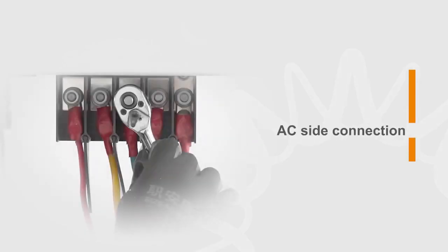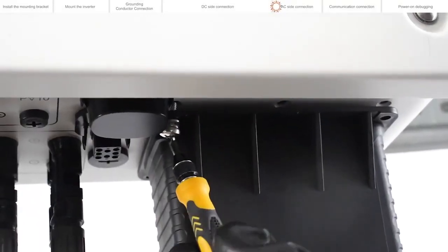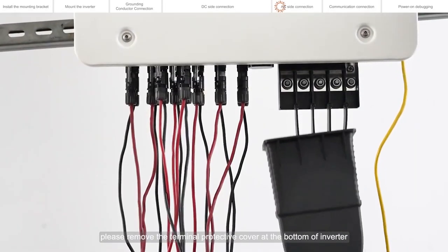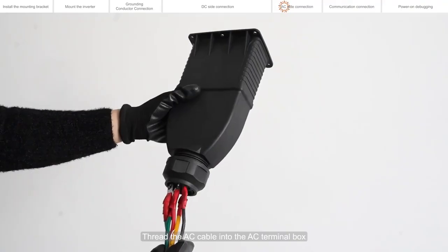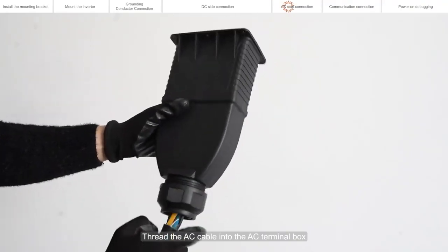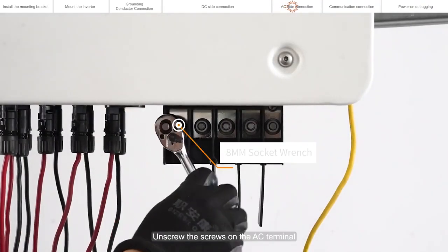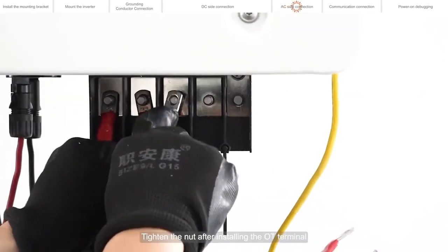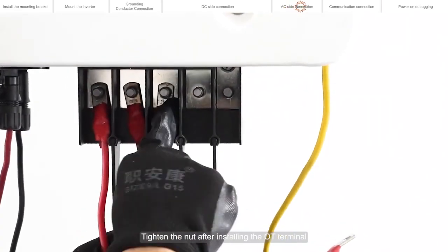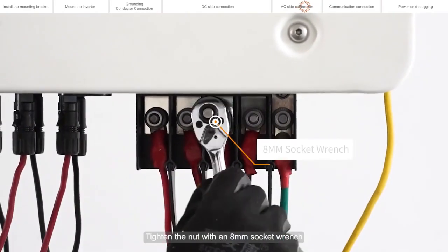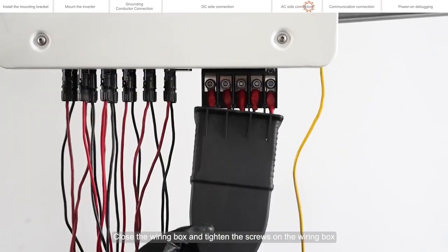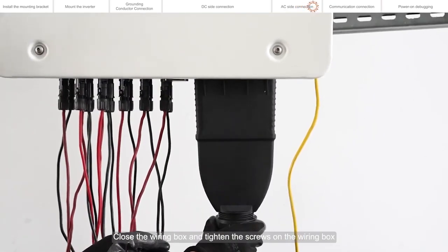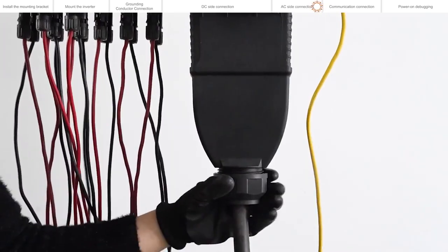AC side connection. Before connecting AC cables, please remove the terminal protective cover at the bottom of inverter. Thread the AC cable into the AC terminal box. Unscrew the screws on the AC terminal. Tighten the nut after installing the OT terminal. Tighten the nut with an 8 mm socket wrench. Close the wiring box and tighten the screws on the wiring box.